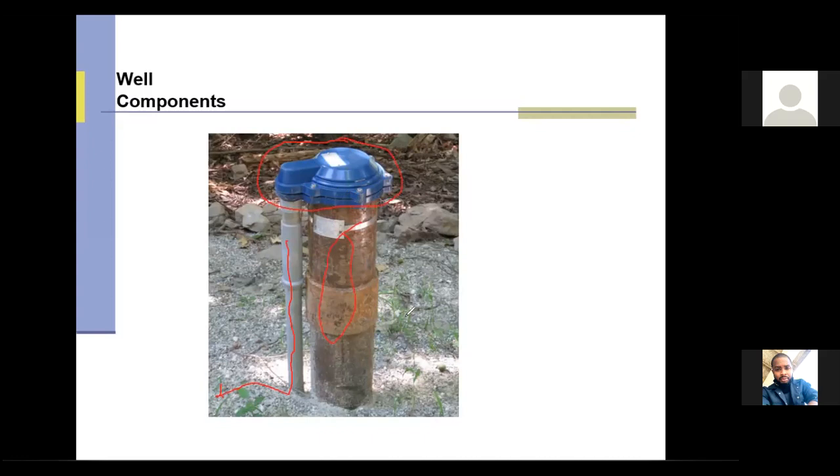What I like about this well here is that it's not low, right? So if it flooded in here, there wouldn't be a problem. Water would never get into the top of this well, and you don't want that. If water gets in the top of that well, that can cause some really big issues, and that's definitely something you don't want. These are your main well components.